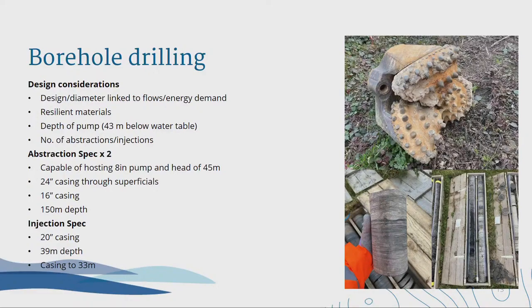In terms of the design considerations, when we work with the local authorities, one of the first questions we ask them is, how much heat do you want to produce? Then we can work that back to a flow rate. So for every megawatt, if you're taking 4 degrees out of the water, you're going to want a flow rate of 50 litres per second for every megawatt. So we start off with that sum first.